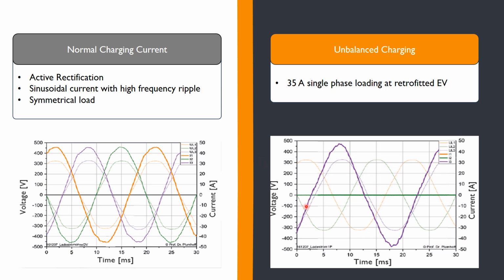So here we had more than 35 amps on a single phase, with also some phase shift to the capacitive load, which is normally not allowed to be connected to a public grid, because you have to take care to symmetricize your loads. But at some vehicles we saw this kind of strange behavior. For mass-produced electric vehicles though, charging voltage and current looked generally like this.